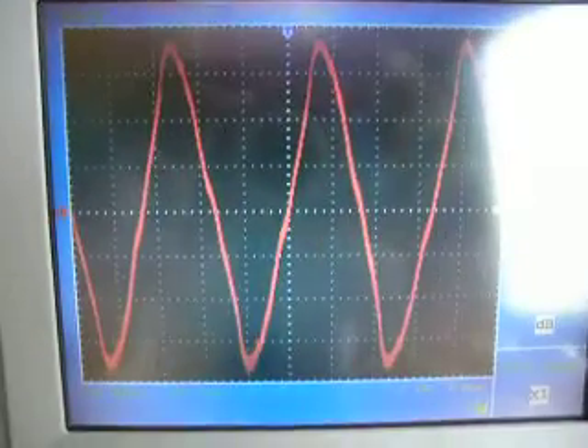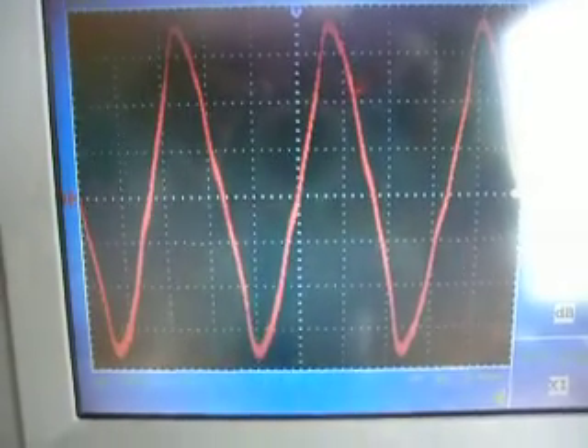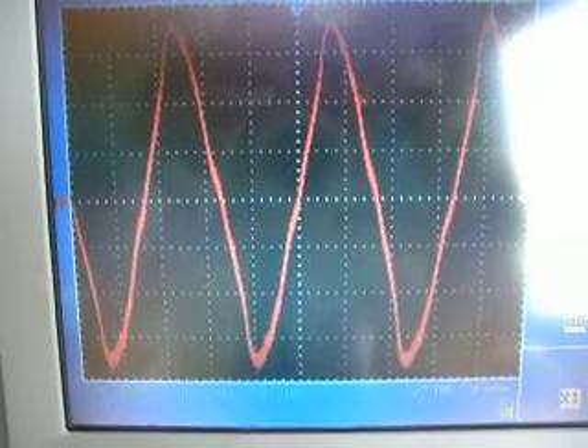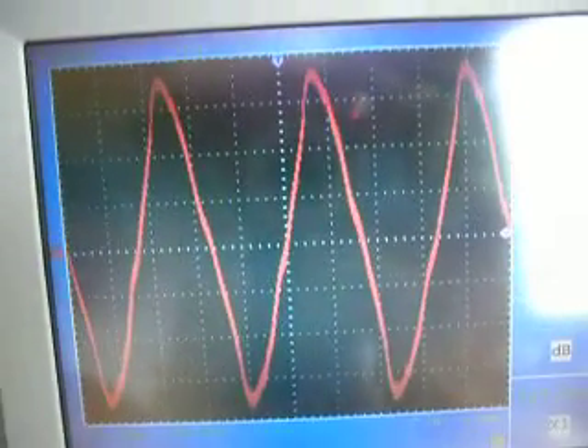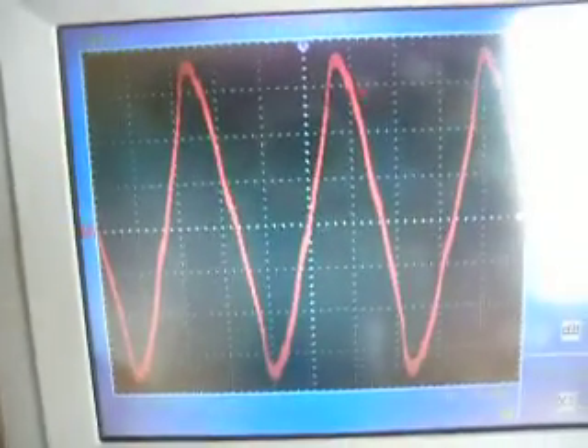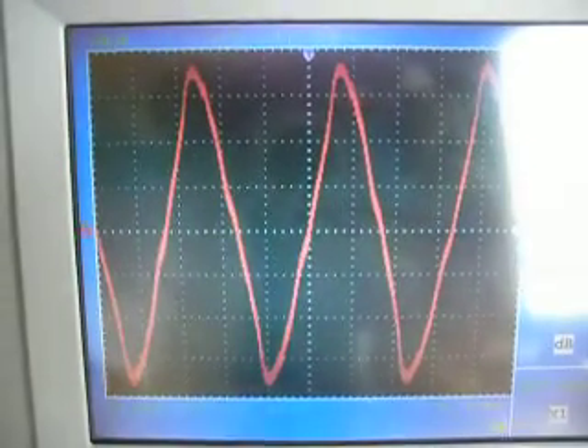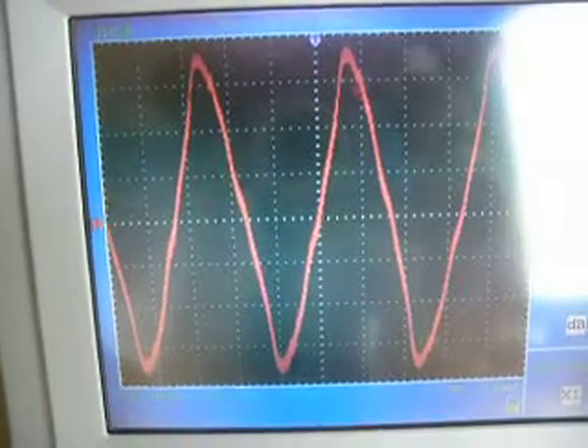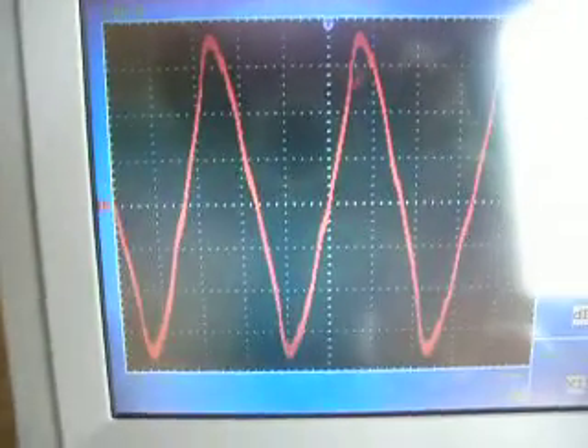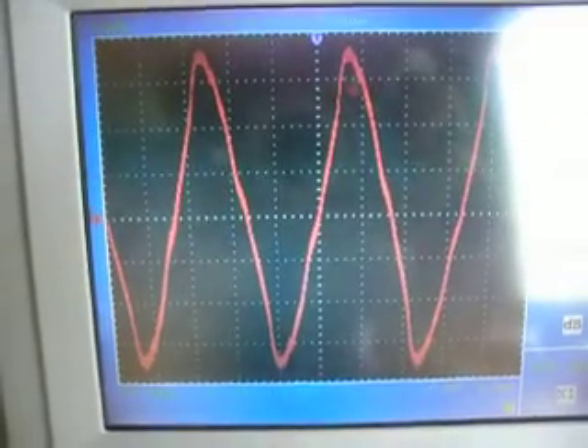So pretty much at 4 volts AC peak to peak, we're on 500 millivolts per division in the vertical direction, and 5 milliseconds per division in the horizontal direction. So what we're looking at is 60 Hertz AC on the utility system grounding connection.